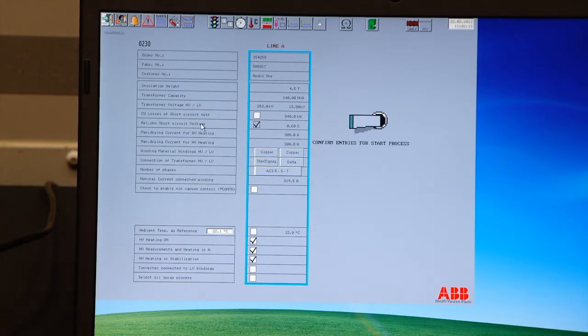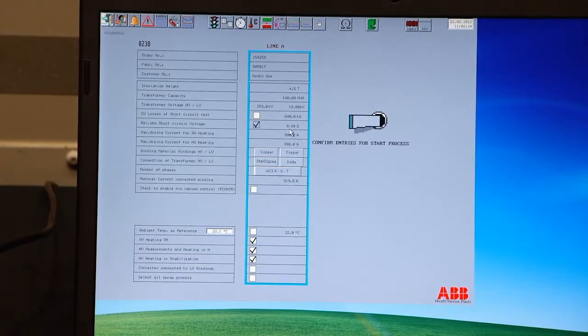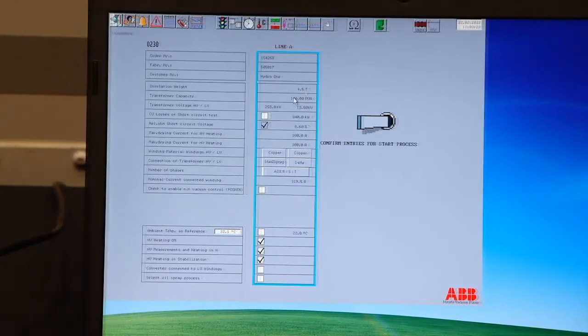Next, we're coming to the copper losses or short circuit resistance losses during the short circuit test. This can be difficult to find, but a good estimate is 0.6% or 0.5% if you don't know it, for power transformers of the rated power. It's better to have a lower value than a higher value. What you do is go to this number, click on it, and enter your values. Now it's 140 MVA, let's say it's 150 MVA, and you click and enter. The value is changed. Go back to our 140 MVA. That's all coming from the transformer data sheet.